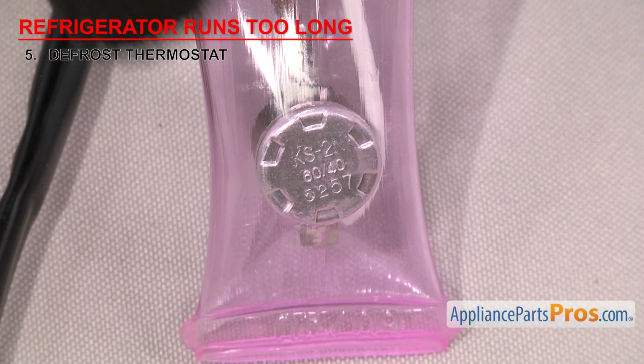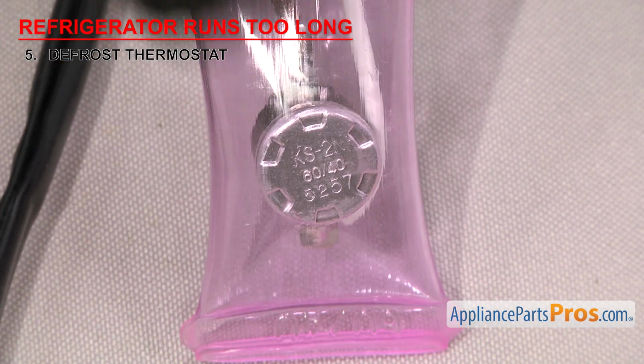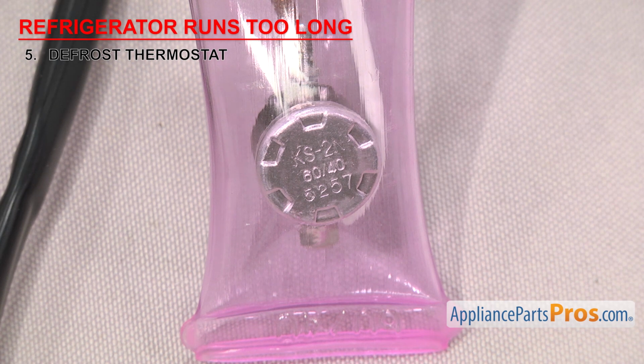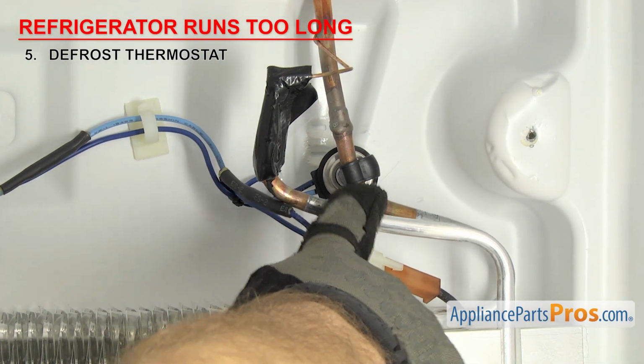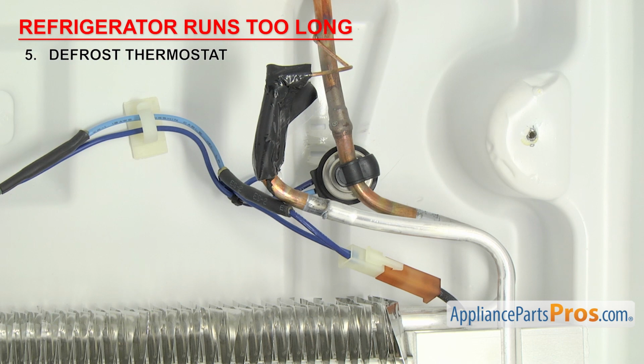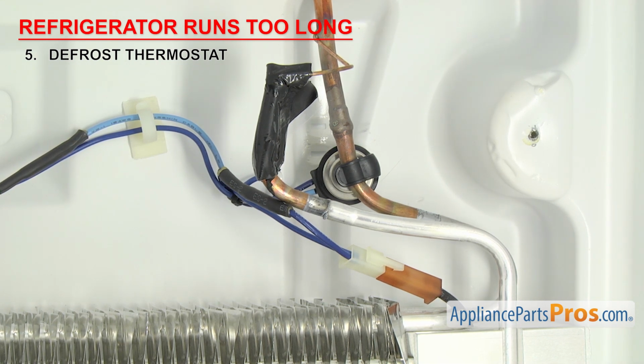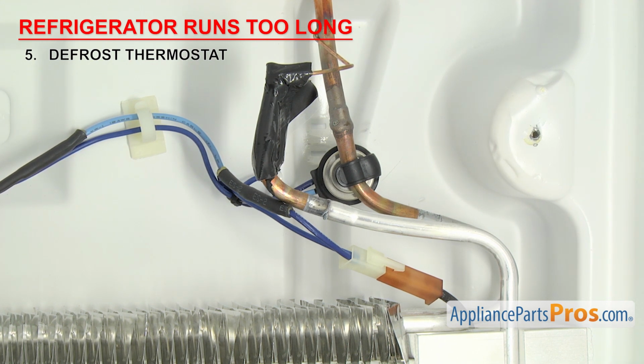This one's rated at 60/40 Celsius. That means it shuts the power off at 60 degrees Celsius and turns the power back on when it cools down 40 degrees Celsius below that, at around 20 degrees. Once the temperature goes below that, the power to the heater is restored. The thermostats are usually mounted behind the back wall of the freezer section on the evaporator. If the refrigerator is running too long, it could be that the thermostat has failed and power isn't being sent to the defrost heater. When this happens, the evaporator freezes up and cold air can't be circulated properly.